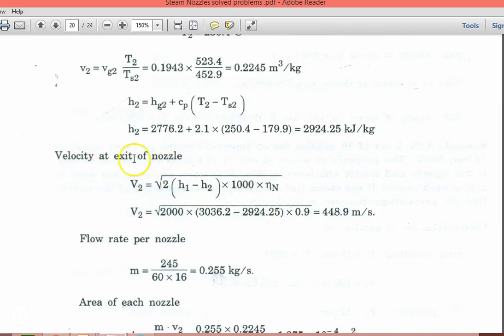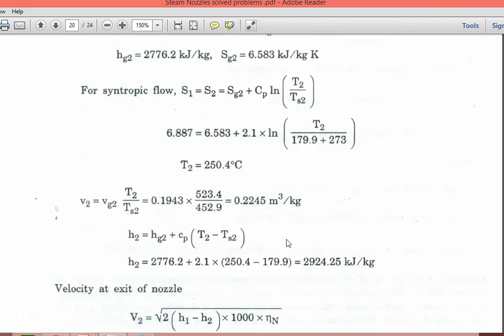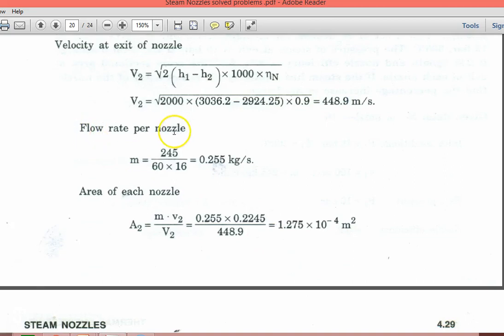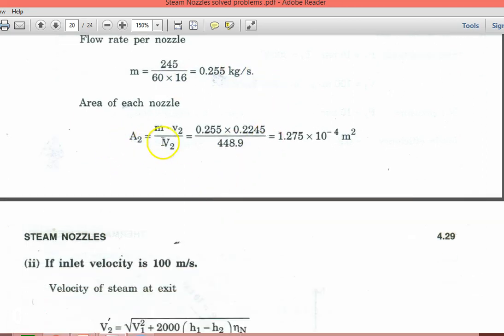Velocity of steam at exit: V2 = √(2000×(H1−H2)×nozzle efficiency). So V2 = √(2000×(3036.2−2924.25)×0.9) = 448.9 m/s. Mass flow rate per nozzle = (245/60)/16 = 0.255 kg/s. Exit area per nozzle: A2 = (mass flow rate × specific volume at outlet) / velocity at outlet = 1.275×10⁻⁴ m².